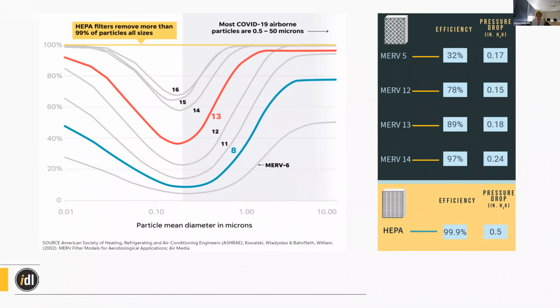And as you go up in MERV rating, you go up in particle efficiency, or filtering efficiency, I should say. So COVID, even though there are different numbers, the virus is about 0.1 to 0.5 microns in size. But the good news for us is that usually viruses aren't just floating around naked in the air. They are actually sort of globbed onto respiratory droplets or different pieces of dust and pollen in the air. So that filter efficiency isn't quite as straightforward as maybe it sounds, but lucky for us, viruses glob onto other things more often, and we can filter those out.